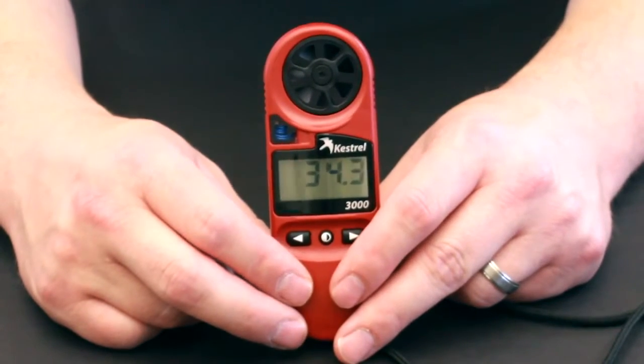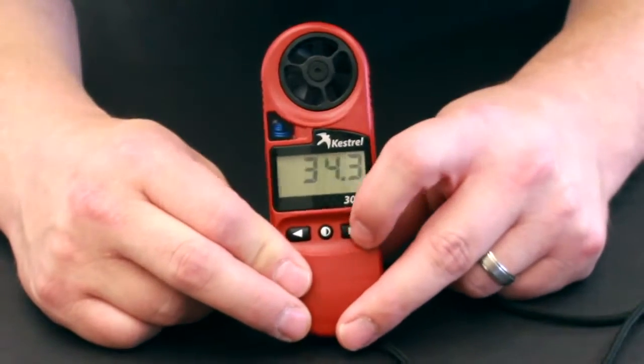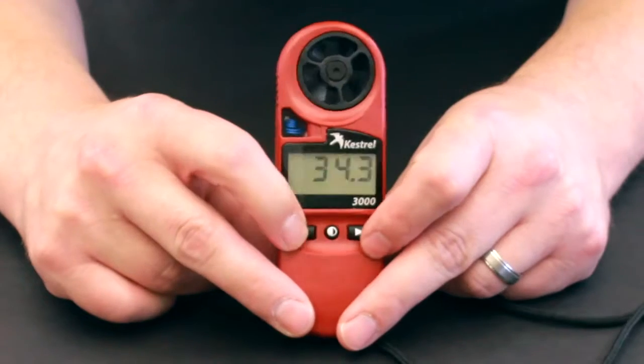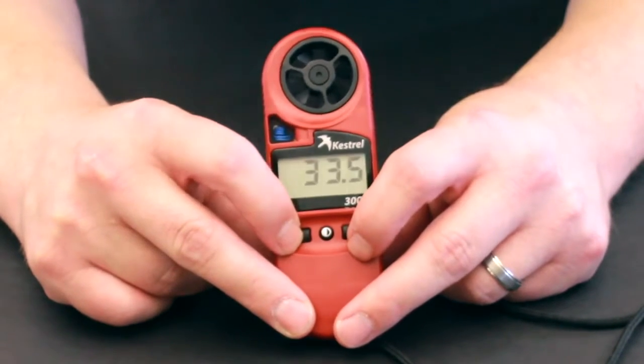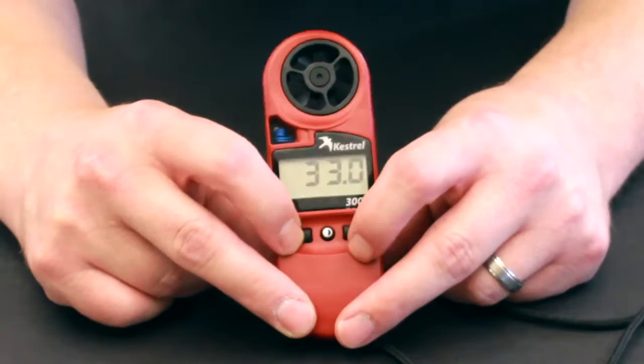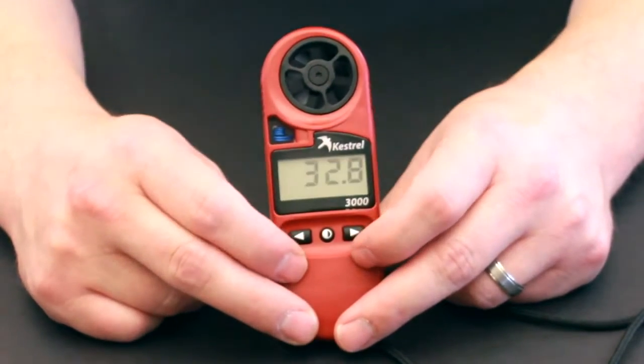Now we have to enter the first value of the first chamber. It should be programmed in. We hit the center button and we see that it displays 34.3. We need to make this 32.8, so we're going to hit the left button until it goes down to the proper humidity for the first chamber.